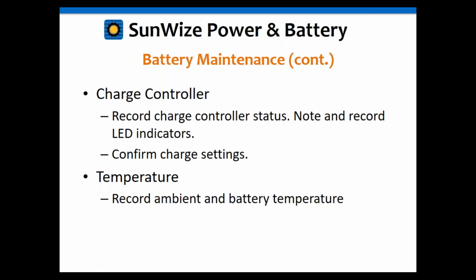Also, you want to record the temperature while you're there, so that you can do calculations to check those charge set points. Those charge set points should be temperature corrected. So in order to double check and make certain that it is charging correctly, you need to be able to do some calculations with regards to temperature correction, to make sure it's correcting it as it should and that the values are right.